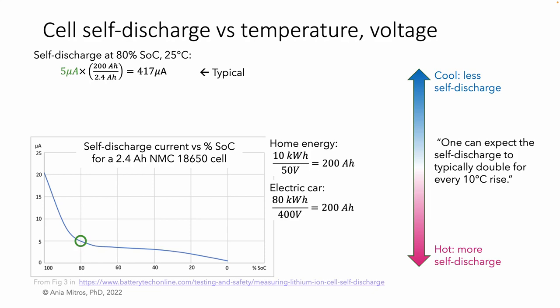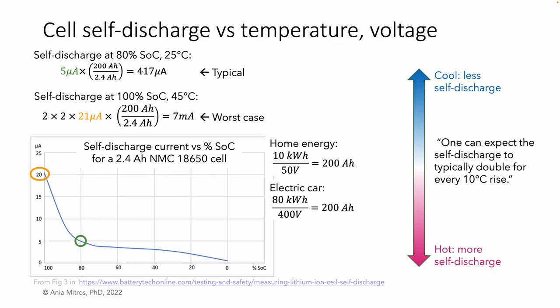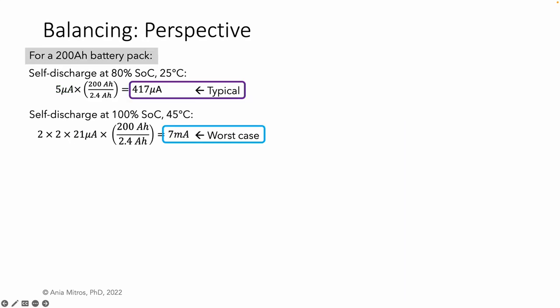If a 2.4 amp hour cell self-discharges at 5 microamps at 80% state of charge, then a 200 amp hour battery will self-discharge at 417 microamps. Our worst case corner is at 100% state of charge and hot, say 45C, where we estimate self-discharge to be about 7 milliamps. Take a moment to compare those numbers to other currents around the battery pack.